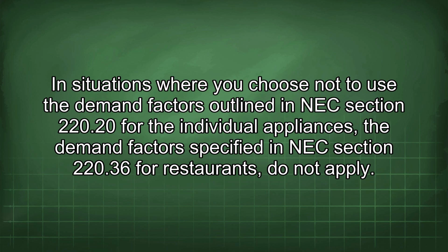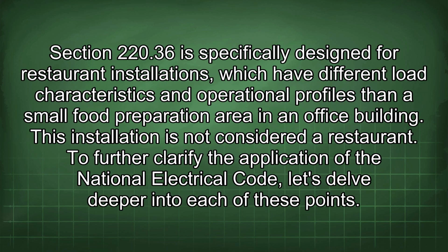In situations where you choose not to use the demand factors outlined in NEC Section 220.20 for the individual appliances, the demand factors specified in NEC Section 220.36 for restaurants do not apply. Section 220.36 is specifically designed for restaurant installations, which have different load characteristics and operational profiles than a small food preparation area in an office building. This installation is not considered a restaurant. To further clarify the application of the National Electrical Code, let's delve deeper into each of these points.